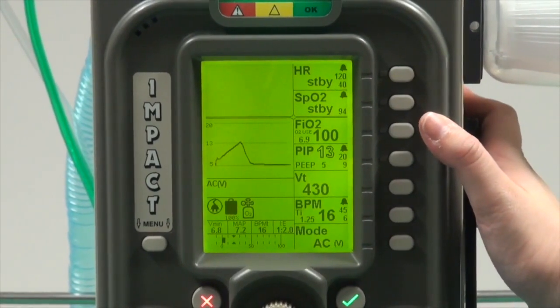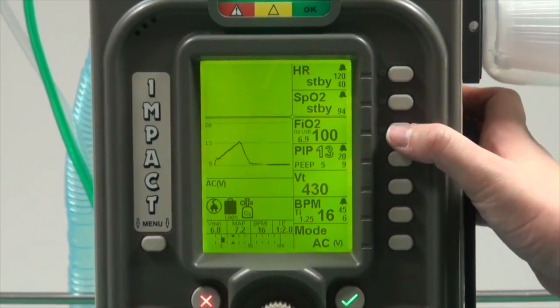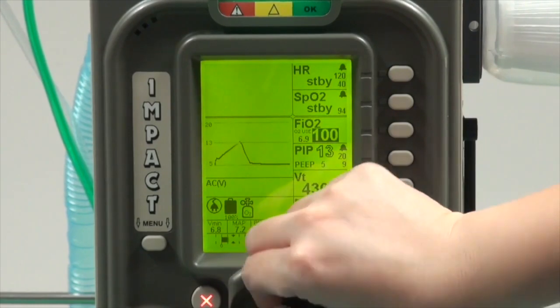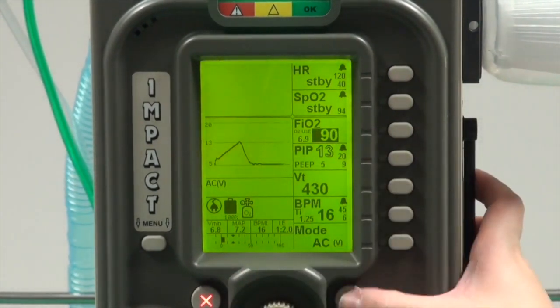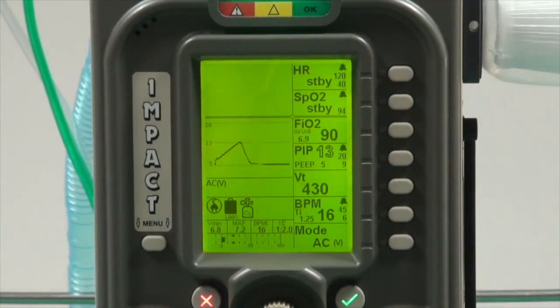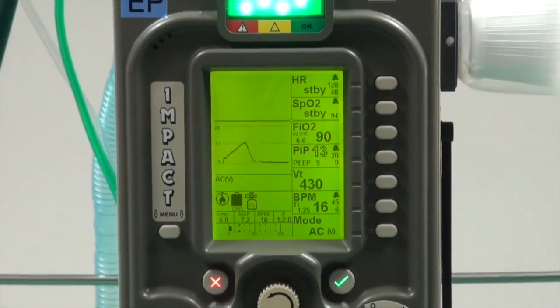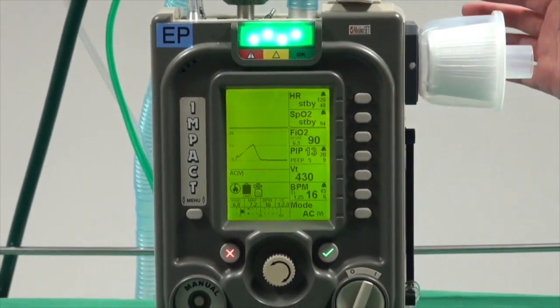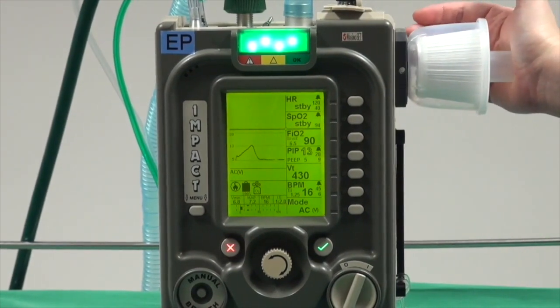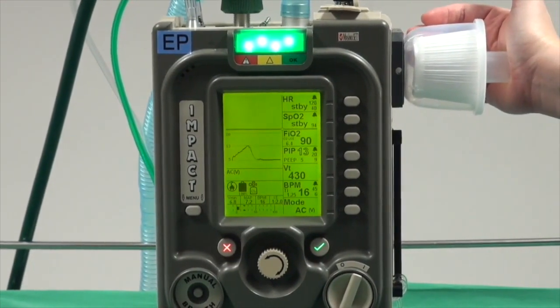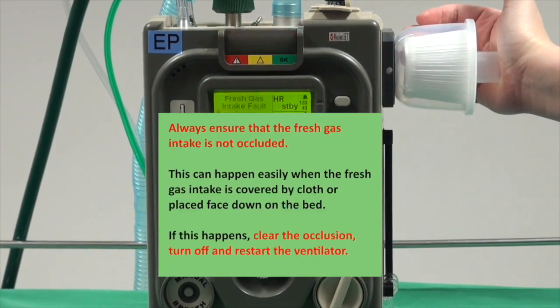One thing to take note of on this Zoll ventilator is if our FiO2 is anything less than 100%, it entrains air from the fresh gas intake at the side. It should not be occluded by any linen, patient clothing, or blankets. Once it's covered, a red high alert comes on. The only way you can resolve this alarm is to turn off your ventilator and restart it.